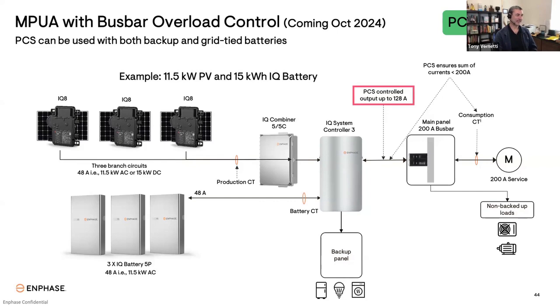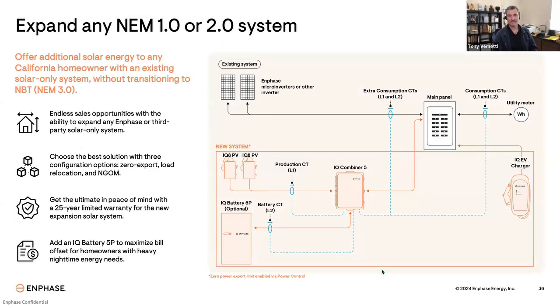Where there is the need for an additional CT is with expansion systems as well. This might have been what Kyle was asking about as well. With expansion systems, we have to install an additional set of CTs to monitor the existing or the legacy PV system. So that's pictured here on the top. That's the only interface that we have with the legacy system. We don't have any means of controlling or stopping power production of the legacy system, but we do require the installation of CT so we can monitor how much power is being produced at that moment and compare that to the consumption CTs. That determines basically how much power the new system is able to produce without exporting to the grid.